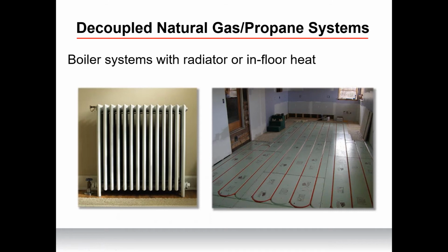If you already have a whole home primary heating source like a boiler, you can utilize an air source heat pump for cooling and as a secondary source of heat. Depending on the age and condition of the boiler, you may want the air source heat pump to be the main source of heat and only utilize the old boiler system as an emergency backup. So think of some existing homes that have very, very old boiler systems or very old piping systems or failing piping systems. It wouldn't necessarily make sense to repipe the entire house, but if that is a functioning system, maybe leave it and utilize that as an emergency backup with a cold climate air source heat pump.